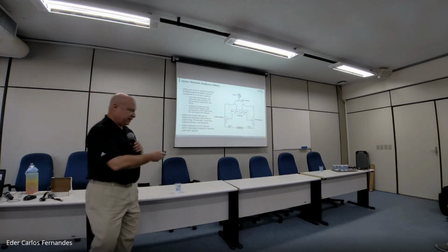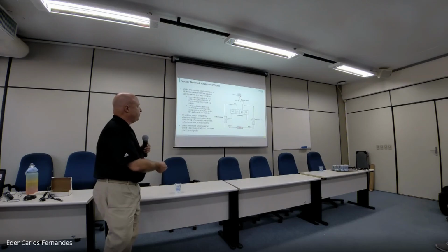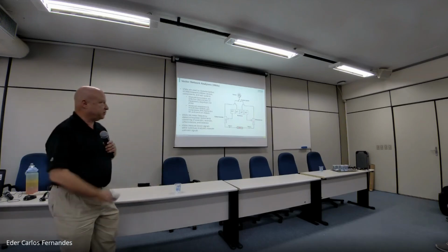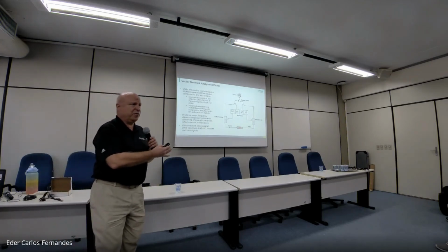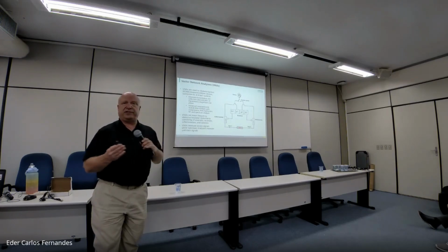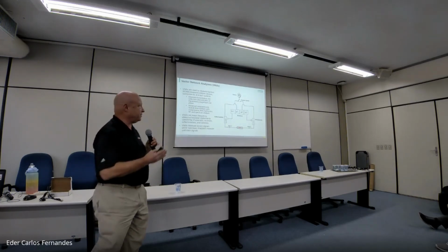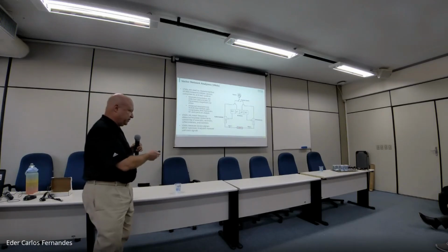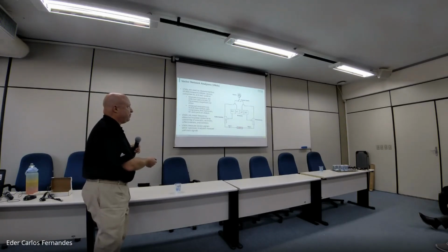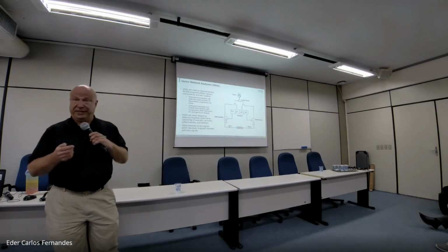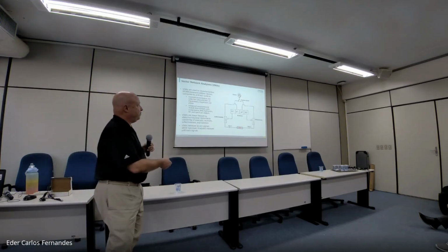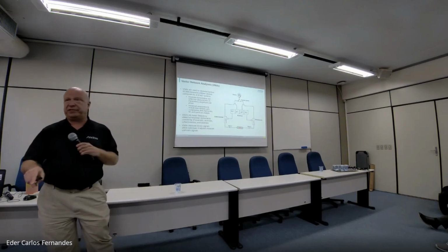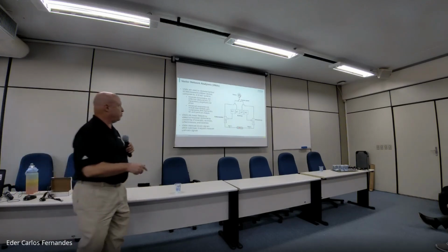And we place that device between the 2 ports so that the device receives the stimulus, something gets reflected back, something gets transmitted across, and through these reflectometers, which are directional couplers essentially, we're able to separate the transmission from reflection signals and analyze them independently. And we also have a couple of receivers dedicated to just grabbing a reference, so we know what we sent in the first place, and then we measure what comes back through the other receivers. So the A receivers are reference, the B receivers are test, both directions, forward and reverse.